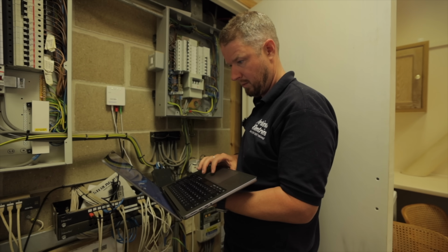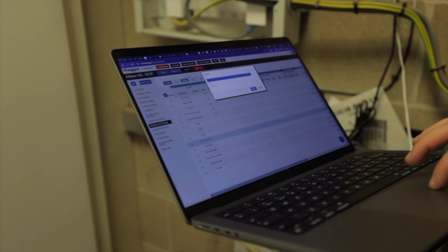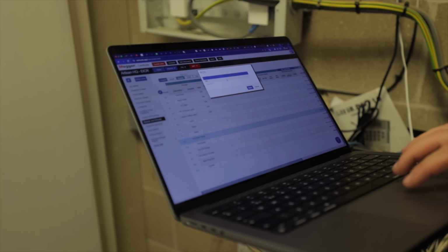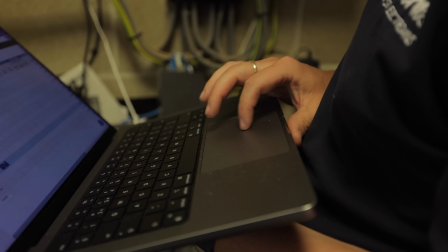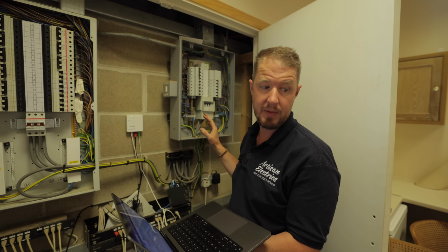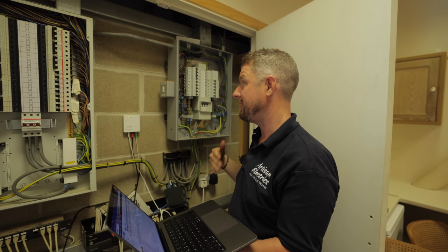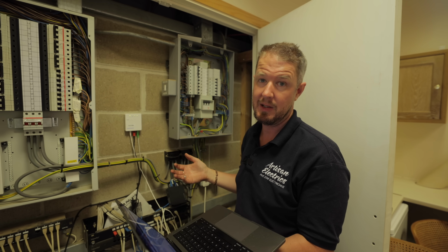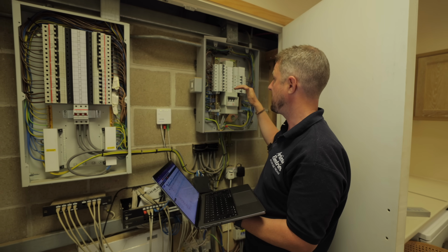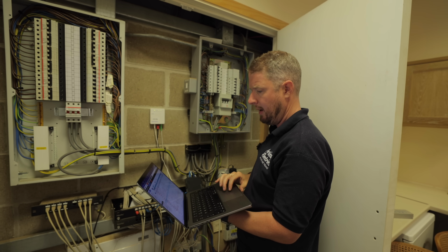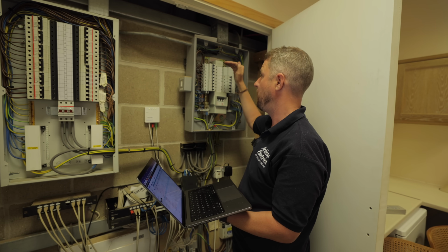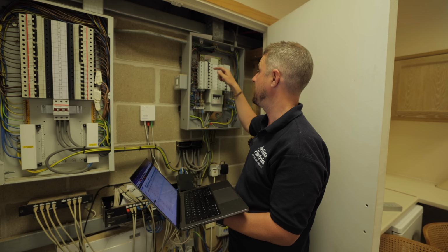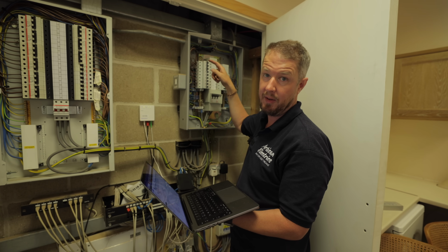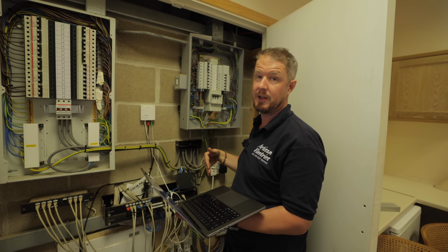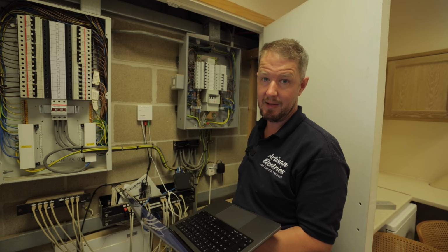So what I'm doing now is I'm just putting in all the circuit details for these boards, just filling out everything I can do in the schedule of inspections. And the nice thing about this property is that everything's quite neatly labelled, so it does save a lot of time when it comes to actually doing the inspection. In here, what we have to do is go through circuit by circuit, put in the type and rating of all of the circuit breakers. We need to put the type and size of the circuit conductors, and then we can start one by one testing all of the circuits.